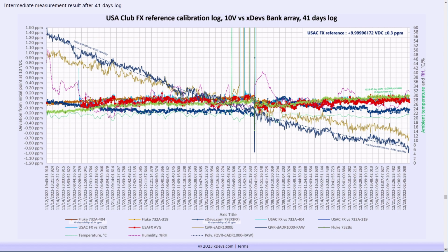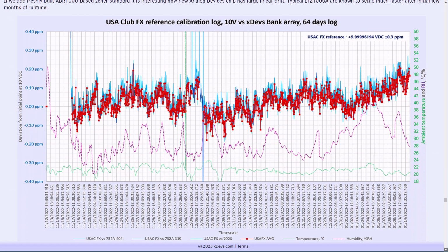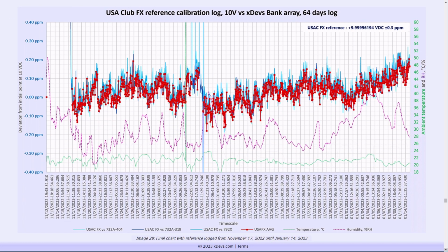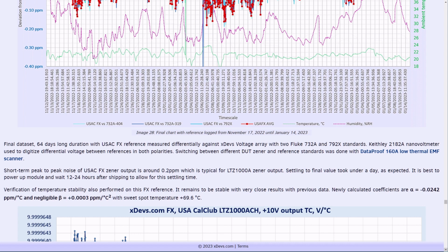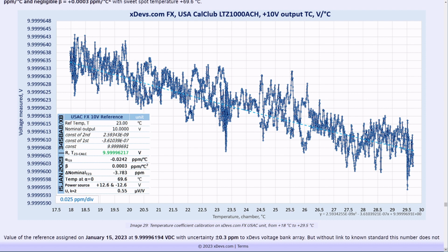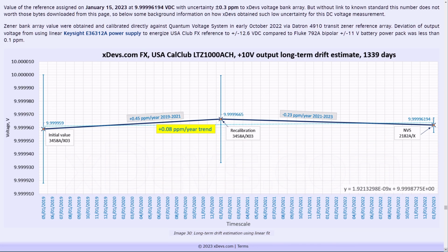Huge drifty line from top left to bottom right is a new reference based on ADR1000 chip. So we can see that new reference is indeed quite drifty and requires a lot of time to settle. And here is the final plot over 64 days collected on USA CalClub FX reference with a vertical span plus minus 0.4 ppm. And of course I tested temperature coefficient of reference to make sure it's still good and happy. So this is the 15 January 2023 calibration with the alpha minus 0.024 ppm per degree. And this is estimated drift of that travel kit reference. So it's pretty impressive, but we need definitely more data points to have a better estimation.